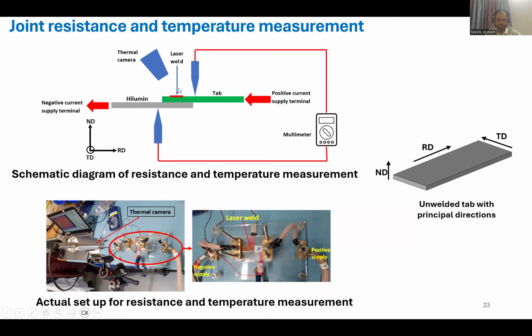At the same time, I am capturing using the thermal camera, which focuses on the weld area only, capturing the temperature range at the weld as current passes continuously. I pass this current for 3 to 5 minutes, capturing the resistance and the real-time temperature simultaneously.